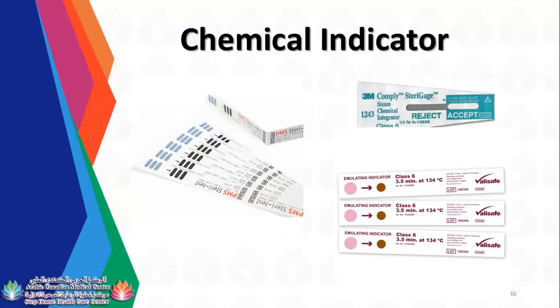So class 6, guys, is actually an emulating indicator. It is a verification indicator, cycle specific, designed to react to all critical parameters in the sterilization process, which are your time, temperature, heat, pressure. Okay? The same with your class 5, which is an integrating indicator designed to react to all critical parameters. Okay, there are times that it will differ. For example, your class 5 will go at a temperature of 132. Okay, it depends. You need to check the IFU for this one.